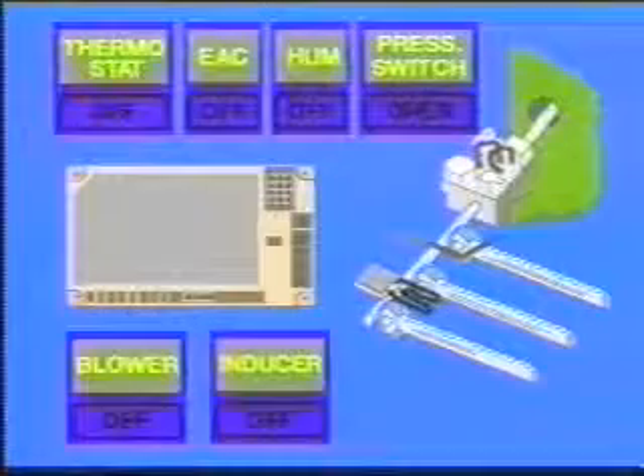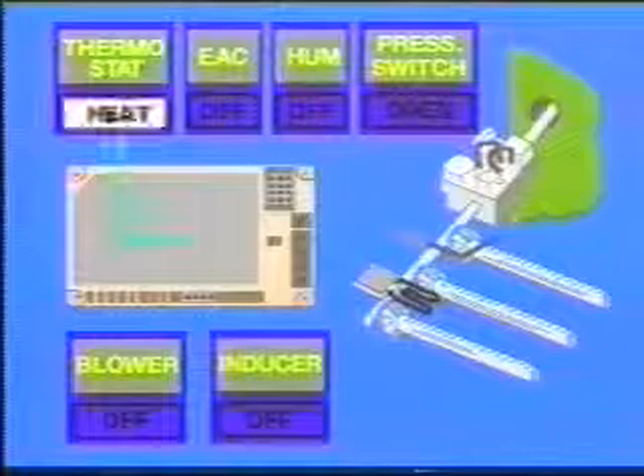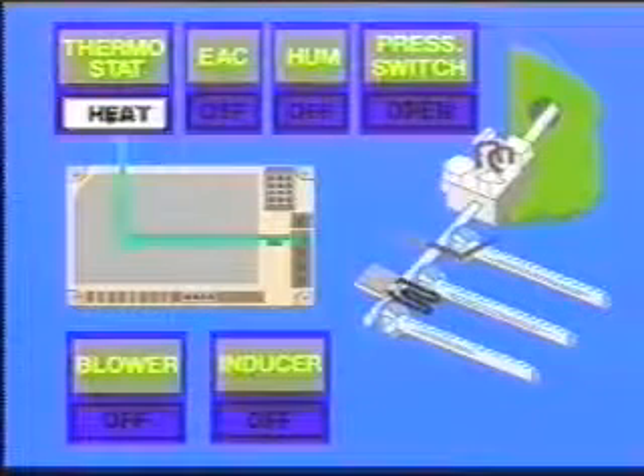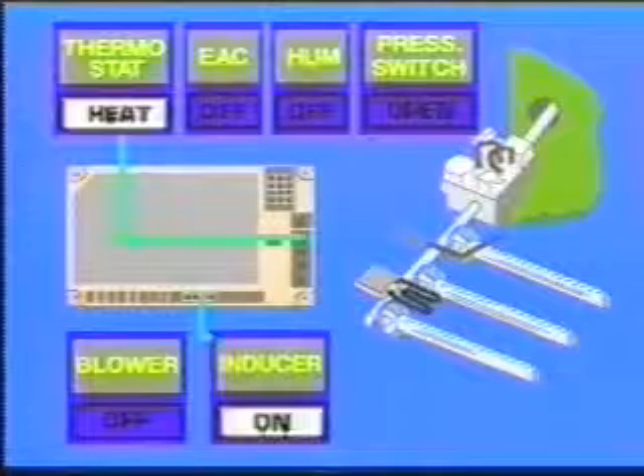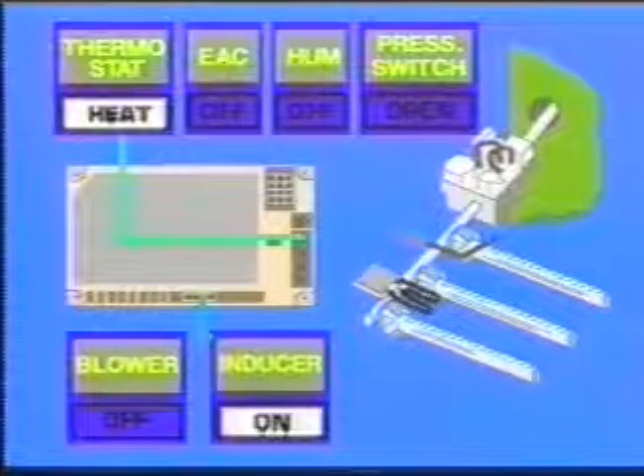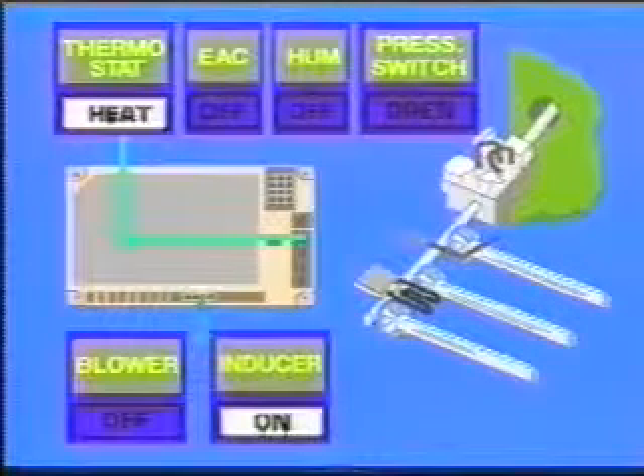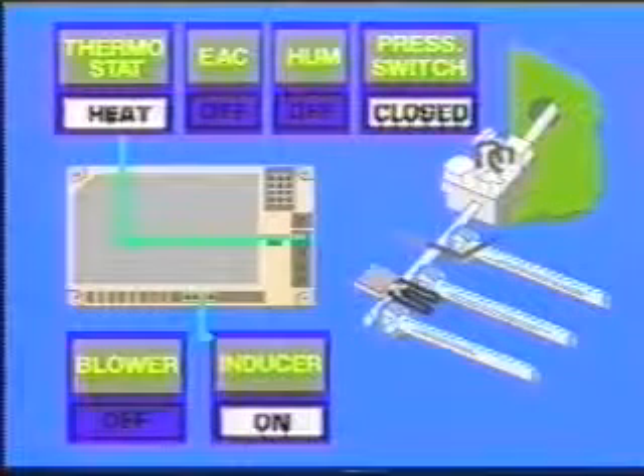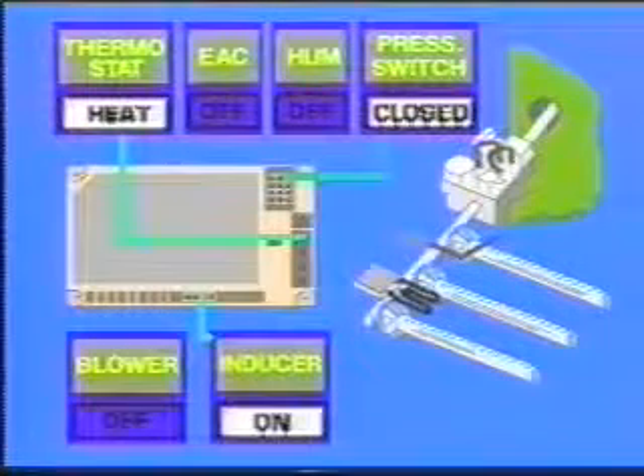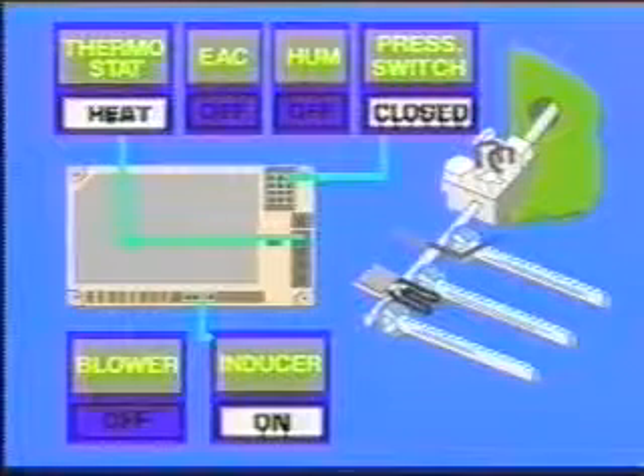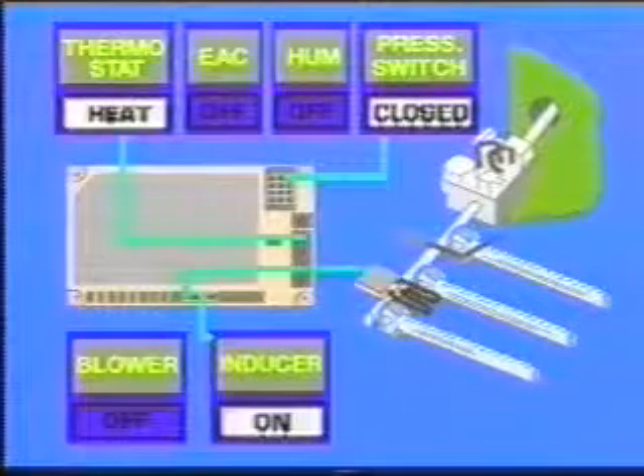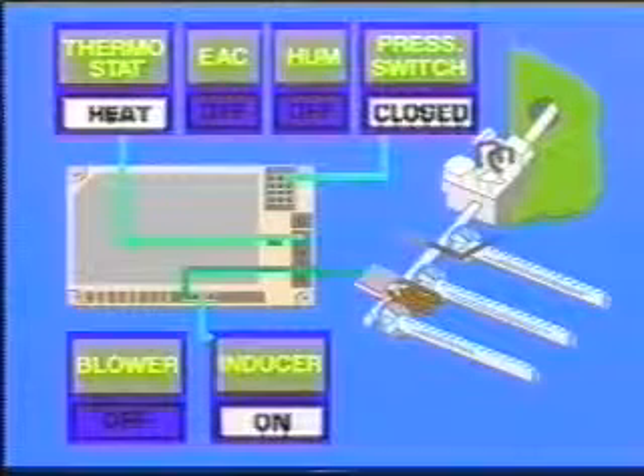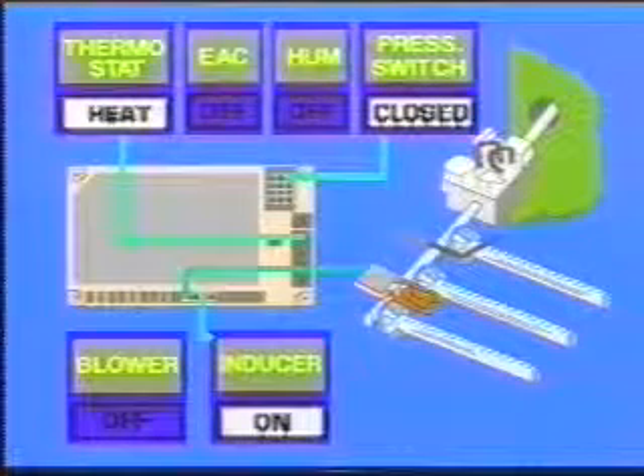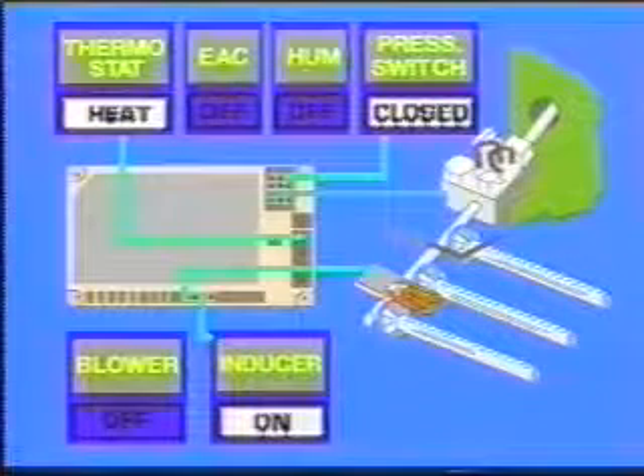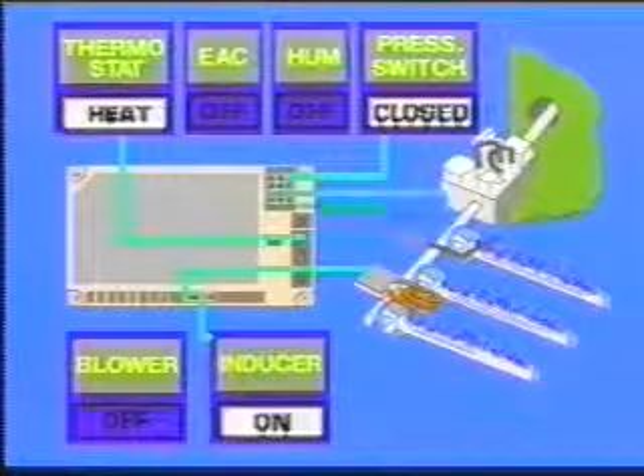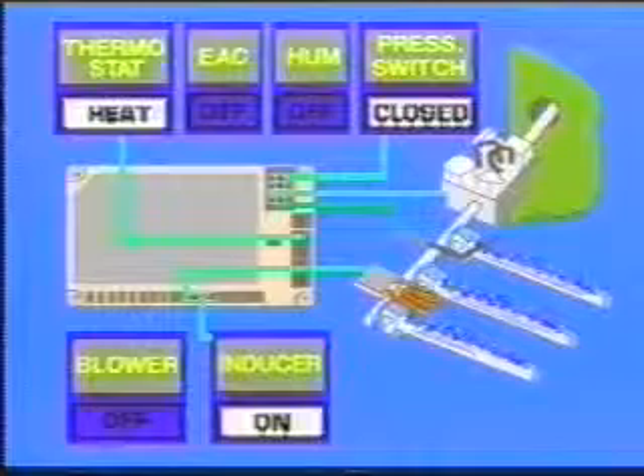The ignition sequence begins when the heating contacts close on the thermostat. The inducer is energized to pre-purge the system for up to 30 seconds. A normally open pressure switch, reading combustion chamber pressure, closes on pressure drop. With the pressure switch closure, the igniter is powered for a 17-second warm-up time. At the end of the igniter warm-up time, the igniter is bright yellow and the gas valve is energized to allow gas flow. The flame sensor must detect flame within 4 to 7 seconds.